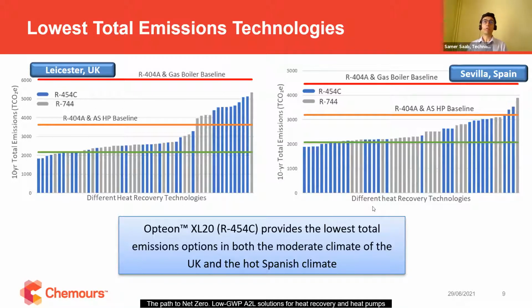But since we are focusing today on emissions, and this is also the path for net zero, to reduce these emissions to the minimum, we have decided to sort these configurations. Each bar in this chart is one different configuration for heat recovery. The bars in blue are for Opteon XL20 or 454C, and the bars in gray are for CO2 or R744.